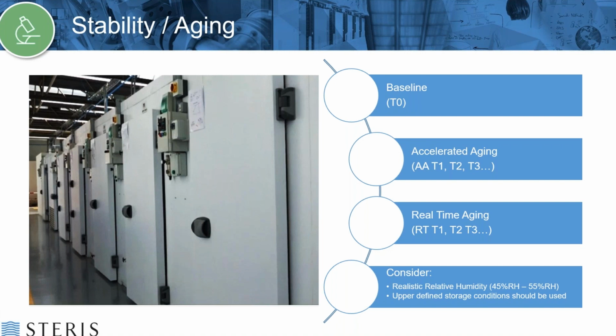And then if you have a defined storage condition, say you have to store your product between 20 and 30 C, the upper defined storage limit should be used in the calculation for your accelerated aging as the ambient condition for that calculation. So that calculation is going to use both the temperature that you're performing the accelerated aging at, as well as that ambient temperature. So if you've got 20 to 30 C for storage of your product, you're going to want to use 30 C for that ambient, as opposed to a 23 C that many people will use.